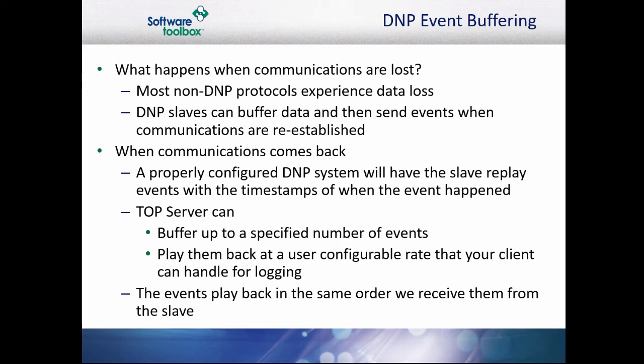Using event buffering does come at some opportunity cost. When enabled, it will introduce latency into the tags of the affected objects. After the initial group of events are sent, new updates from the slave will only be released to the client at the playback rate. Therefore, it is wise to use this feature only when capturing all events is more important than fast delivery of the events to the client.